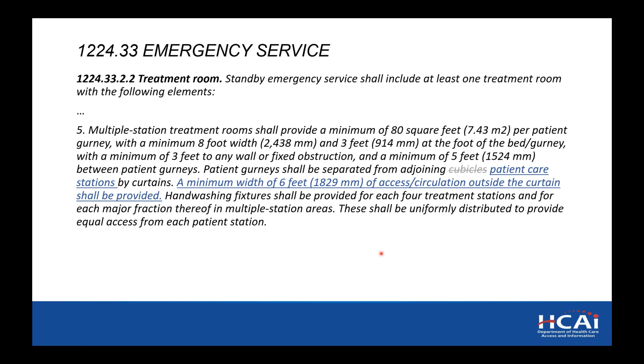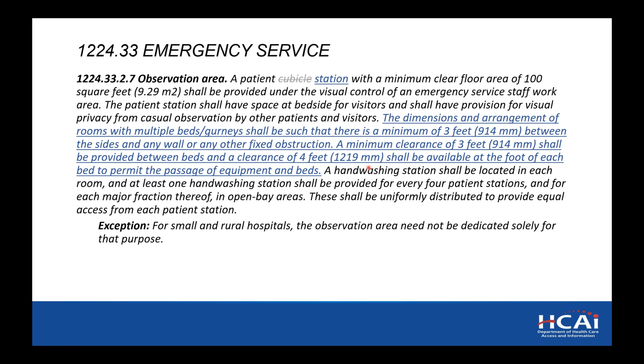For observation area, same thing. There's a little different wording here. For the observation areas, the dimension and arrangement of the rooms, and again, we're trying to align these more with a patient room in this case. You're going to have clearances of 3 feet between the sides and any wall or fixed obstruction, a minimum clearance of 3 feet between beds, and a clearance of 4 feet shall be available at the foot of each bed to permit passage of equipment. Again, if you recognize that language, it's the exact same as for a patient room.